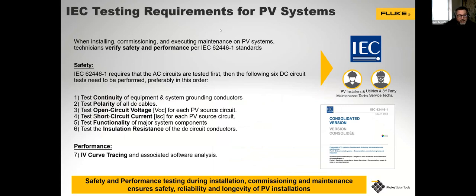It requires that the AC test circuits are tested first, and then the following 6 tests need to be performed, preferably within this order. So we're looking at continuity of equipment and grounding conductors, polarity of all DC test cables, open circuit voltage, short circuit current, test functionality of major system components, and test the insulation resistance of the DC circuit conductors. In addition, what we're going to be looking for is the IV curve tracing, which basically says, are our panels actually performing in the way that we expect them to?